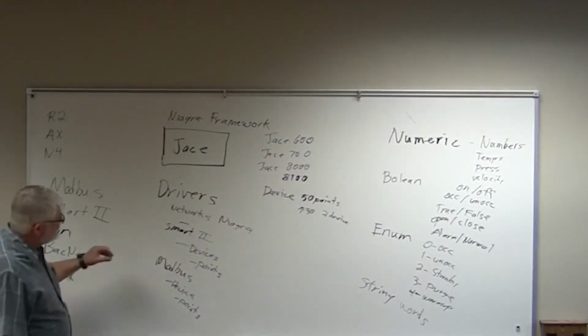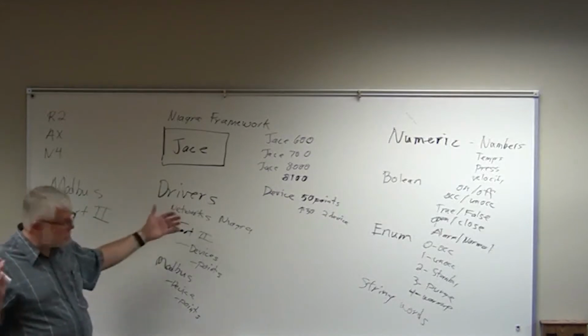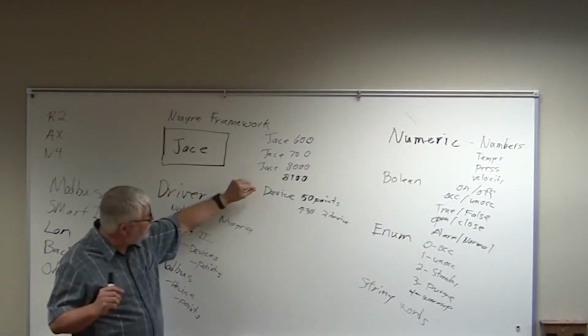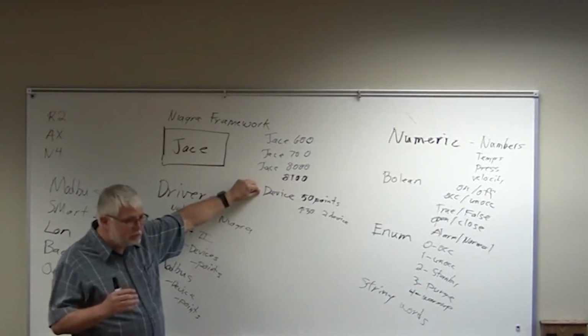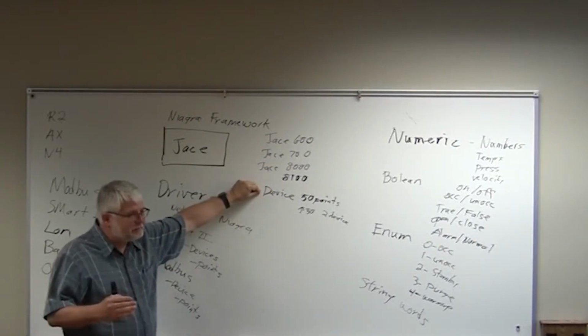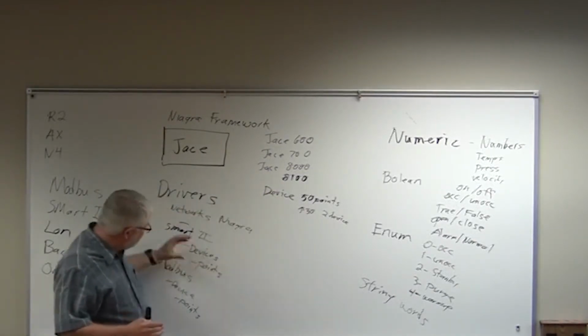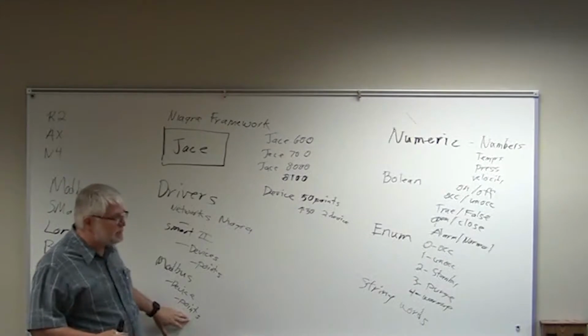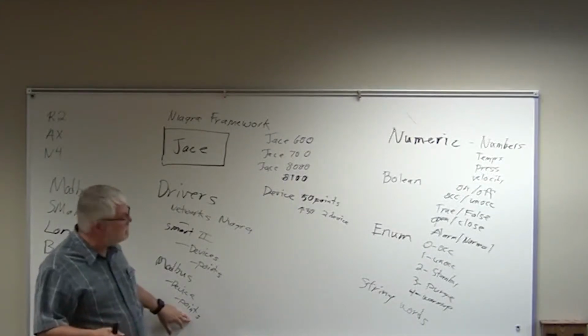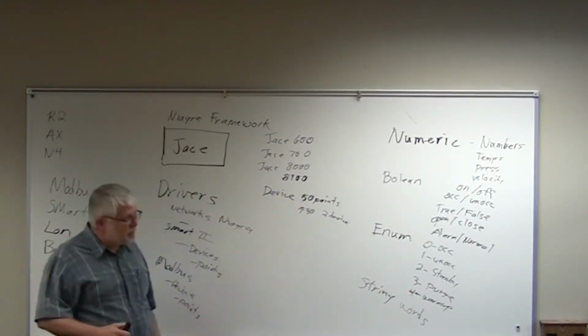So it's physical. Like when we talked about last class, when we landed a wire onto that controller, that's one device. And then underneath it in the database, it'll have a points folder, and as you pull in those points, that's what counts against your 50-point limit.